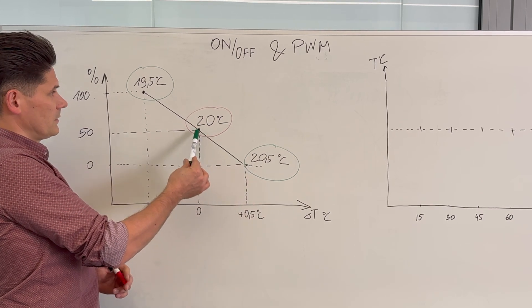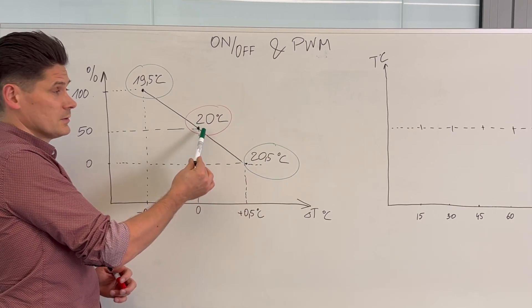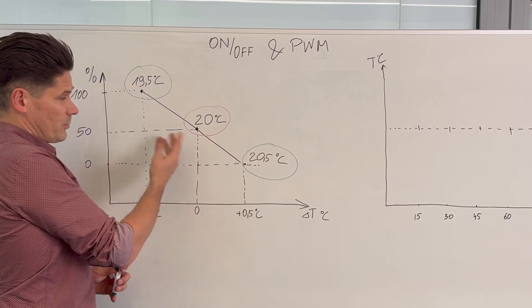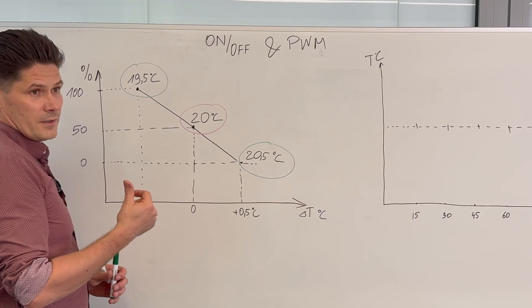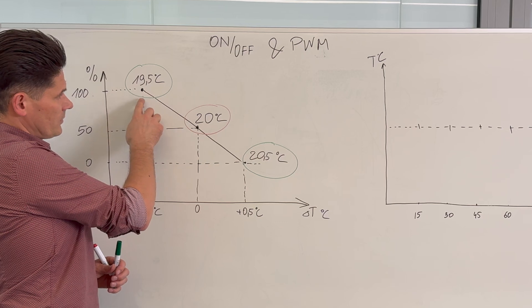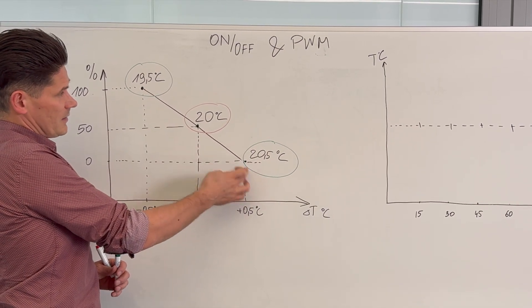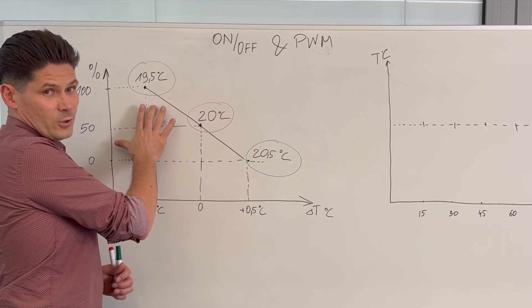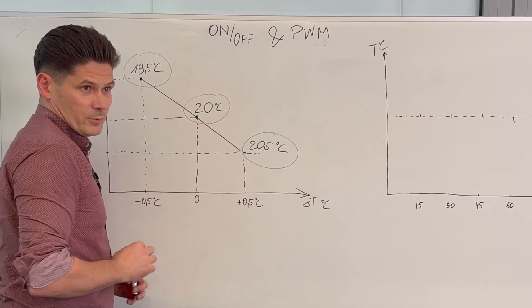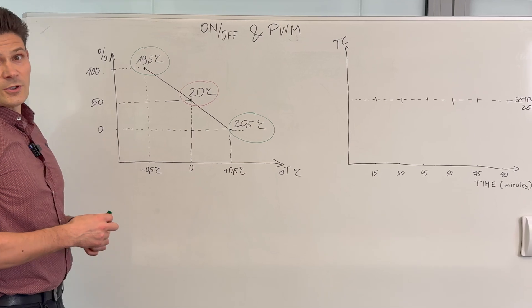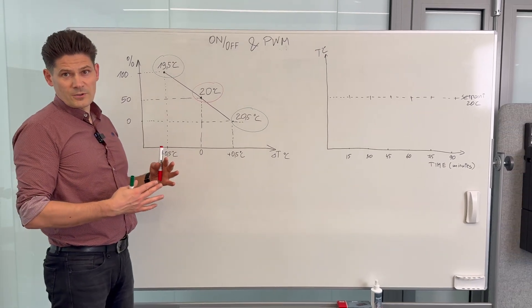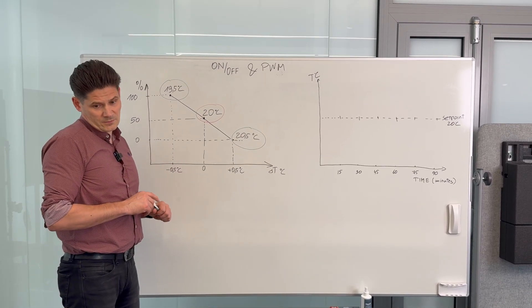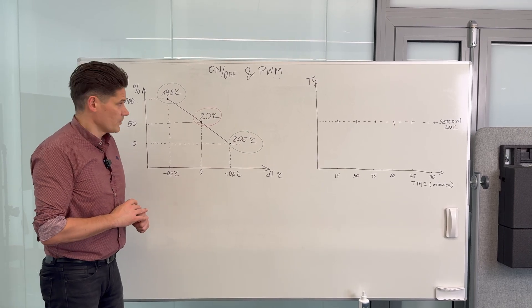The room thermostat is waiting and room temperature goes down - the actuator is still closed. At 19.5 degrees, the thermostat senses the temperature is too low and switches the actuator on again. So coming from higher temperature the actuator is closed, and coming from lower temperature the actuator is open. This is on/off control - it is not very precise but it is a very basic room control.